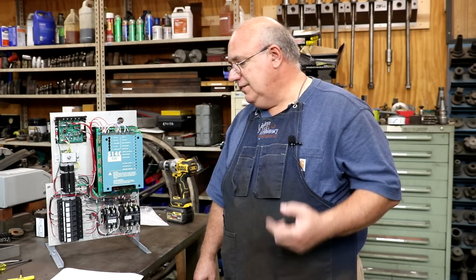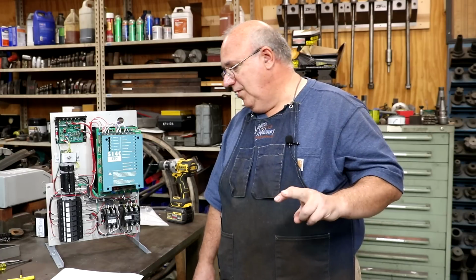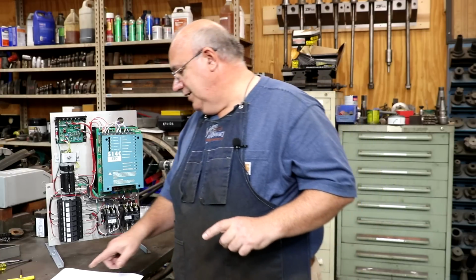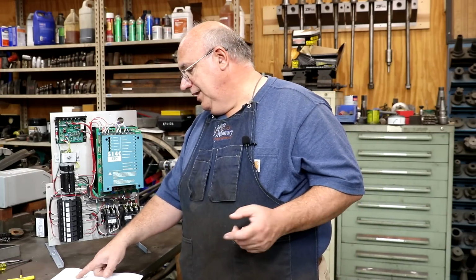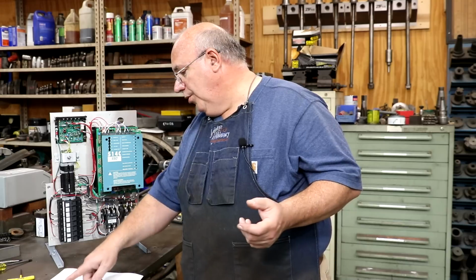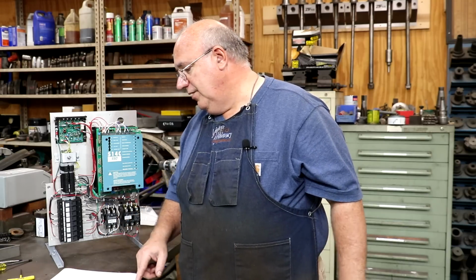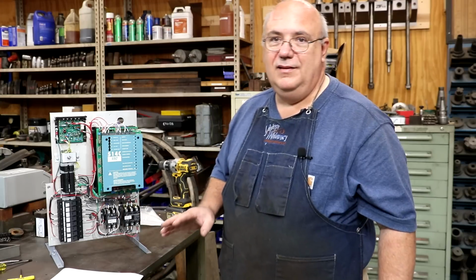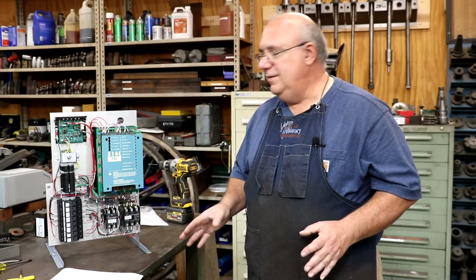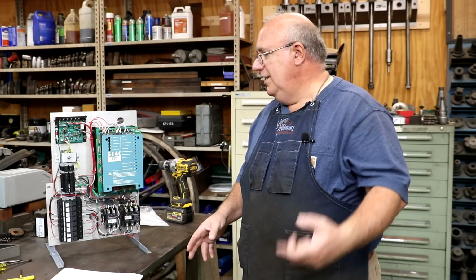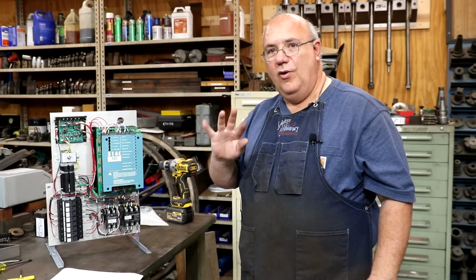On this lathe there's an additional 2 wires for a series field, which gives the motor extra torque by increasing field strength under a heavy load. So it's more complicated than typical, and we're having to control at least 4 different things.